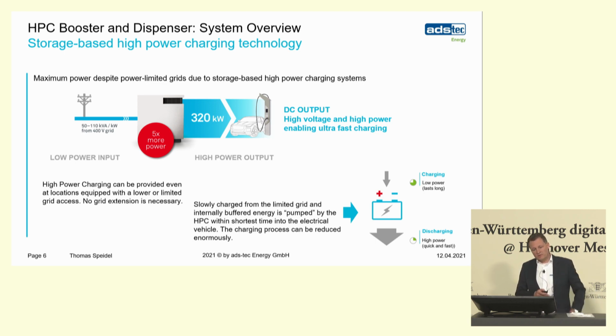If we have only limited grid access and limited power, we use the battery as a buffer. We load the buffer with low power, and once the battery is full, we take the stored energy and deliver it at a higher power rate into the electric vehicle. So we have a boosting process from, say, 50 to 100 kilowatt from the grid up to 320 kilowatt directly to the vehicle.